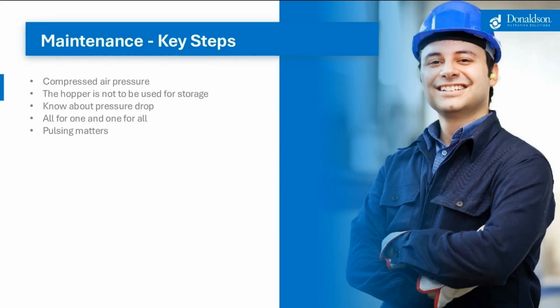Where there are a number of cartridges, bags or panels, when it comes to filter replacement, always change out a full set. It is false economy only changing a few, as when a collector is switched back on, the air and the dust will take the easiest route, overload the new filters, and often you'll find yourself back at square one. Pulsing does matter. It's not only the correct compressed air that's needed, there are many other components of a reverse jet cleaning system that require maintenance and checking, such as pulse valves, solenoid valves, and controller settings. Consider your controller settings for pulse duration and pulse interval, cleaning on demand, and the all-important offline cleaning where possible.